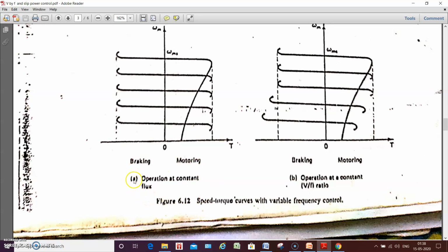It is a direct method of keeping the flux constant by using some methodology to measure and maintain closed loop operation of the flux control. But it is very difficult. In practical cases we go with the V/F ratio control method. So here at the lower speed ranges, the characteristics will be slightly deviated from the constant flux method control.